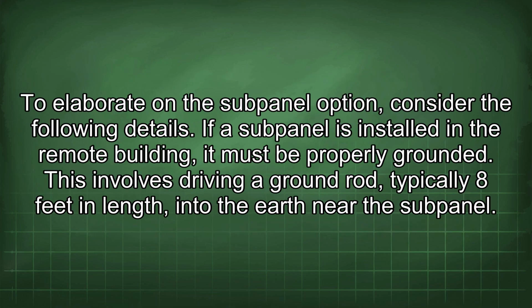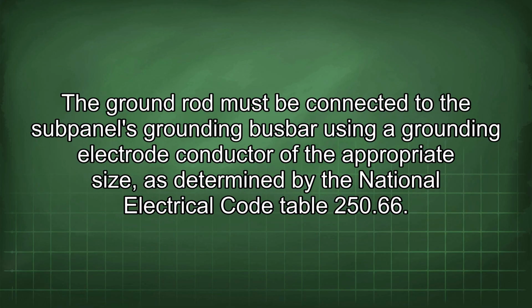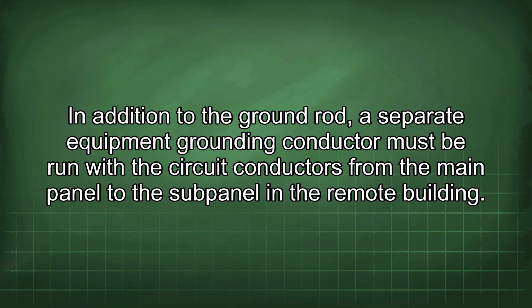To elaborate on the subpanel option, consider the following details. If a subpanel is installed in a remote building, it must be properly grounded. This involves driving a ground rod, typically 8 feet in length, into the earth near the subpanel. The ground rod must be connected to the subpanel's grounding busbar using a grounding electrode conductor of the appropriate size, as determined by the National Electrical Code Table 250.66.